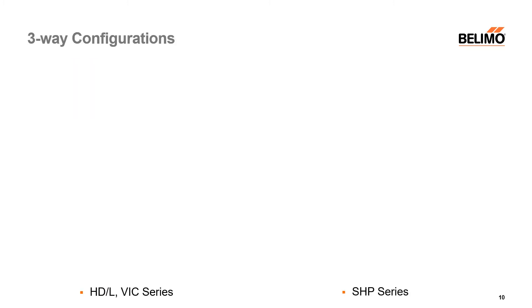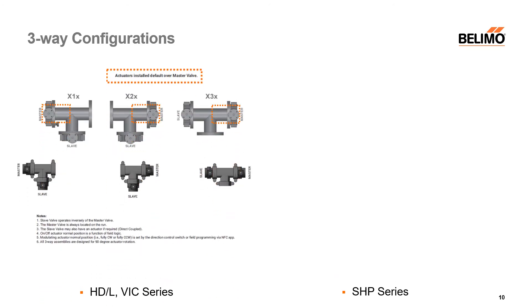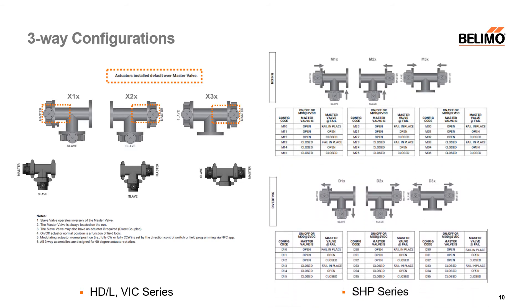We sell three-way butterfly valves that must be ordered in a specific configuration. Essentially we're taking two two-way valves and mounting them to a T. You would need to specify the configuration — X10, X20, or X30 — based on how you want the valves made. The HD and L series can be used for mixing or diverting. The high-performance series is flow-specific because it's a higher-pressure valve and must be made either for mixing or diverting. If ordered incorrectly, you can change them in the field, though it is a bit time-consuming.